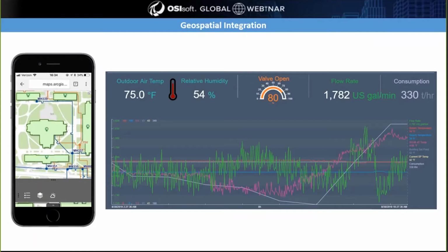Now let's say next week or in 2 weeks, the same environmental conditions and the same level of occupancy exist, but now all of a sudden it's 500 tons per hour. That's something I want to be alerted to, because it means there's a step change in how this building is consuming chilled water. If you don't have this information and aren't monitoring it, how do you find out when there's an issue? How do you identify major passing valves or underground leaks? It can be, and I'd argue maybe it is, impossible without analyzing this data.